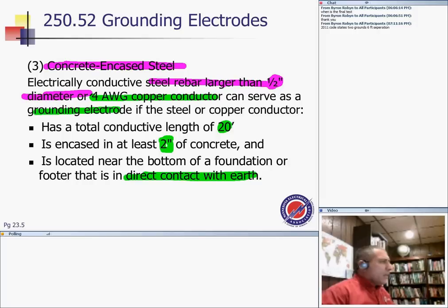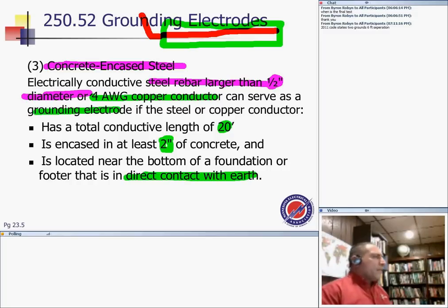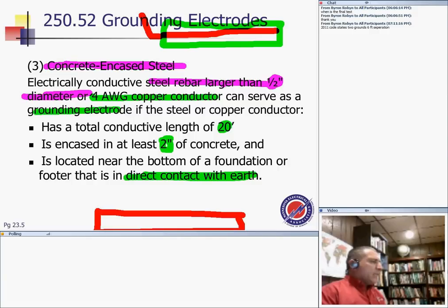For example, Joanne, my friend, you have a beam that's sitting on the 14th floor in downtown Minneapolis, and that beam has a rebar in it on the 14th floor. I can't use that beam as concrete encased steel because it's on the 14th floor, not in direct contact. So the only beam that I can use has to be in direct contact with Mother Earth, as you guys know, because that's where the moisture is. So the right foundation, surrounded by the foundation. So that beam, the concrete encased electrode, is the one that I'm trying to tie to.